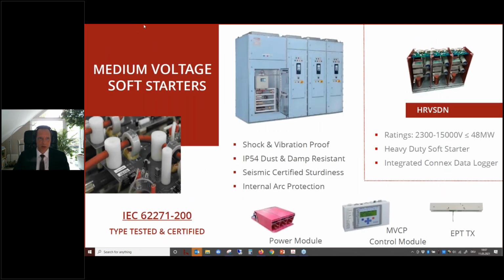Good. Going to the medium voltage soft starters, what you see here is our HRVSDN product. Here in the middle, you see something where you have a soft starter and three motor feeders, which is called multi-start. In principle, it consists of the medium voltage part and the low voltage part, which you see here with the open door, the power module with the thyristors, a control module, and one device, which is called EPTTX, to which I will come in a moment.